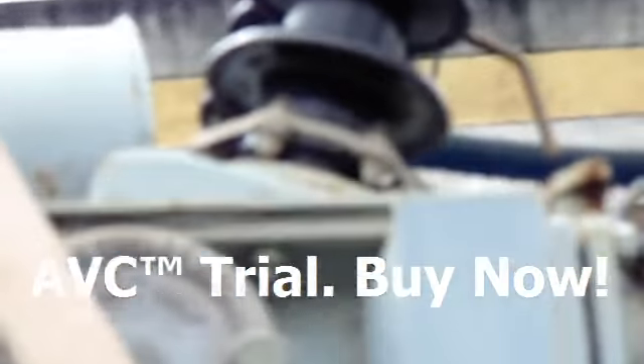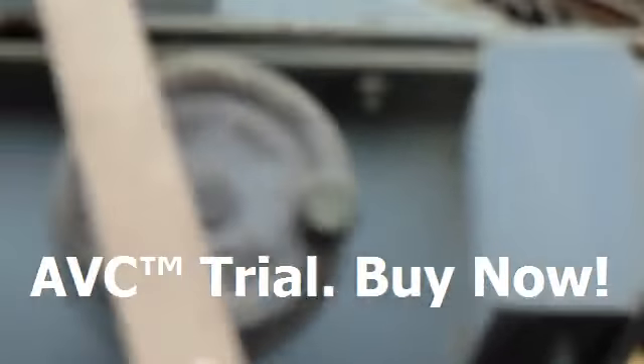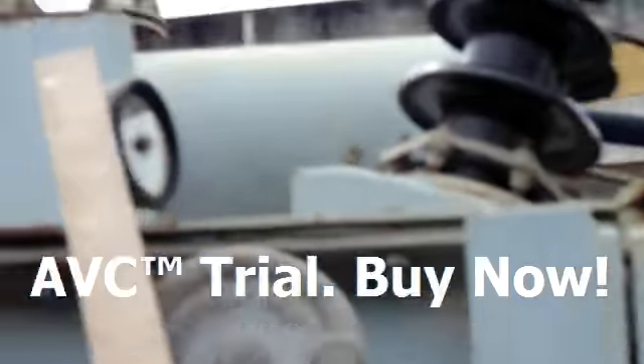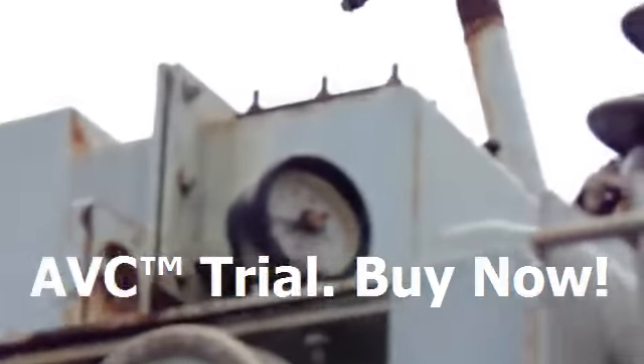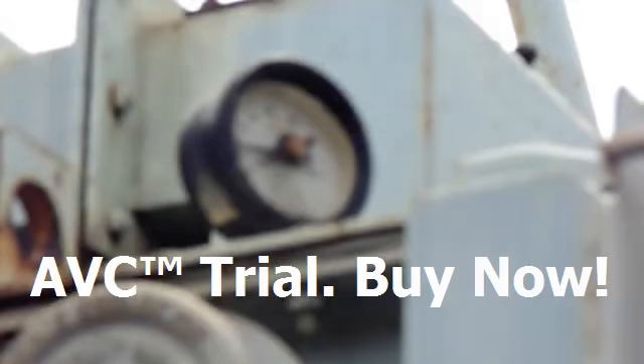As an engineer, you have to make a regular check whether the temperature of the oil is exceeding 80 degrees centigrade. If the temperature of the oil is 90 degrees centigrade, in all means it indicates that the temperature of the winding is more than 100 degrees centigrade. If it exceeds that, then you have to give protection to the transformer. You have to protect the transformer from overheating. That also you have to take care of.